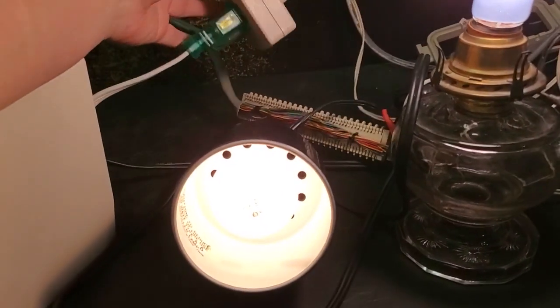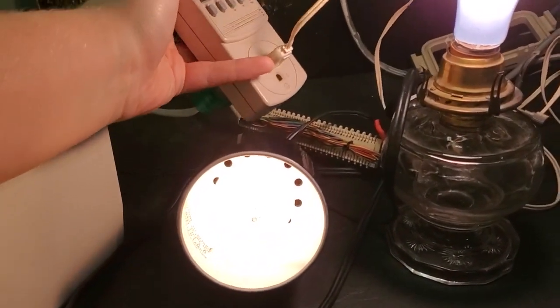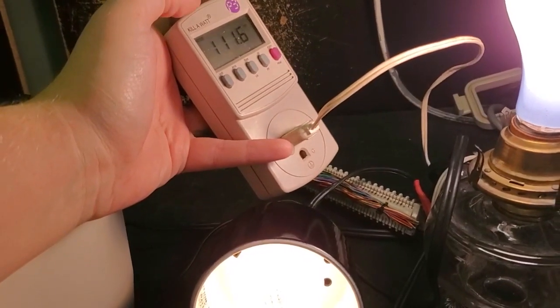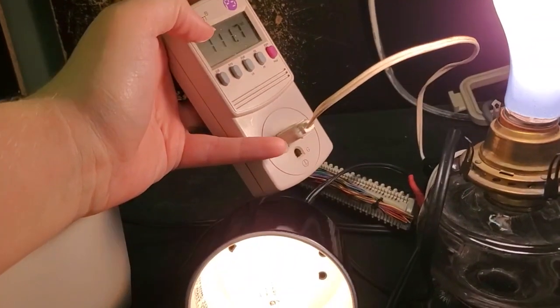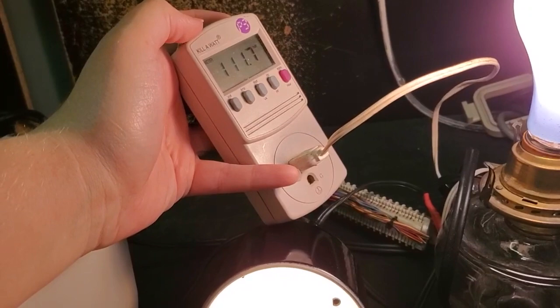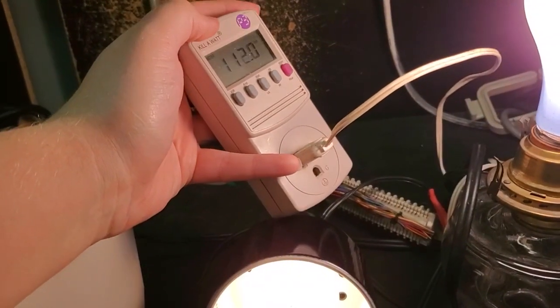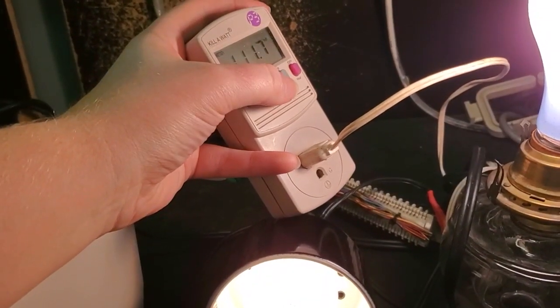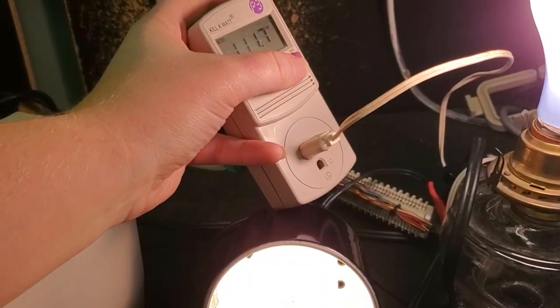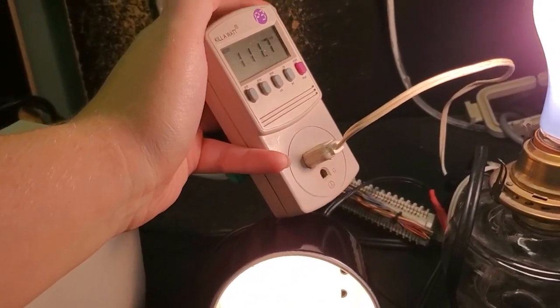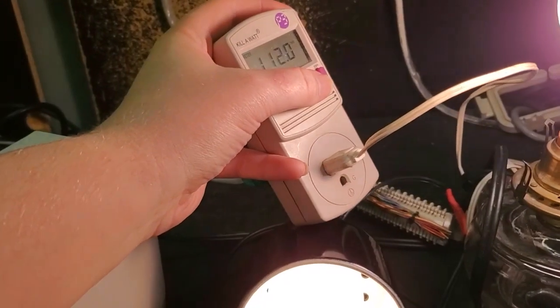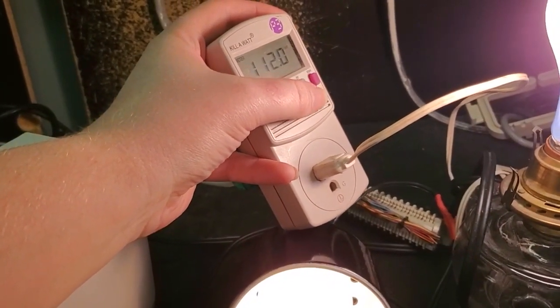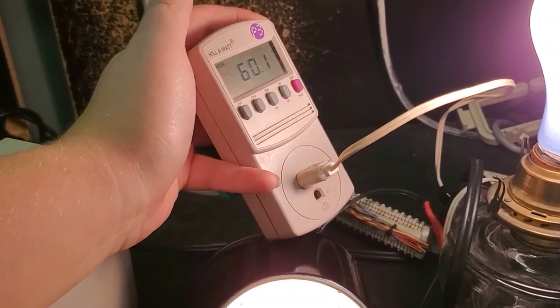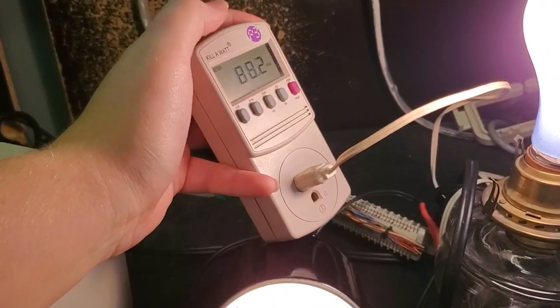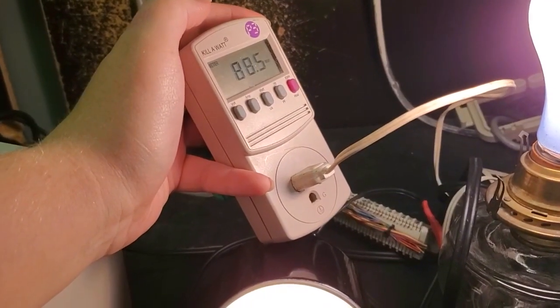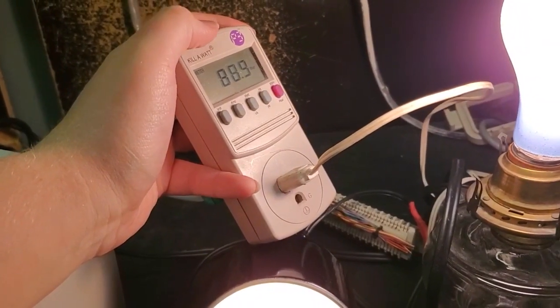I don't think the voltage or frequency wavers at all when this thing's on its inverter, save for that little adjustment in the output voltage it did in the beginning. But there we are—as you can see, we're holding 111, 112 volts. I had originally set it for 110, so it regulates its voltage quite well, after that initial test where it kind of started at 105. Frequency is holding. And actually, because of the lowered voltage, we're only doing 88 watts on this thing.